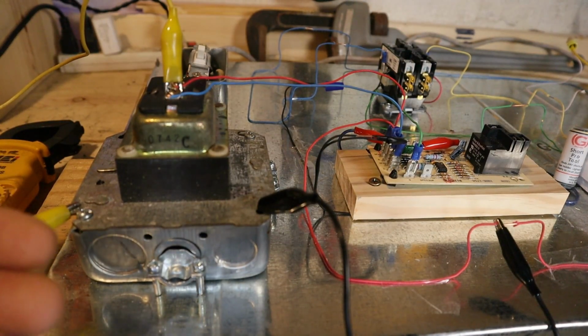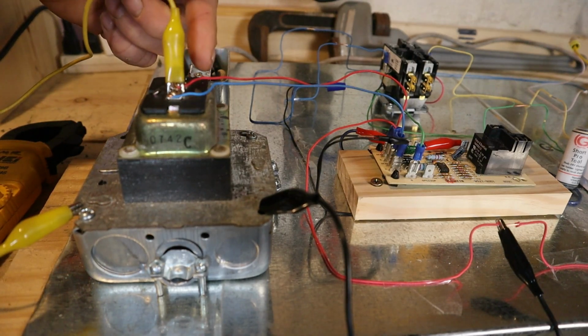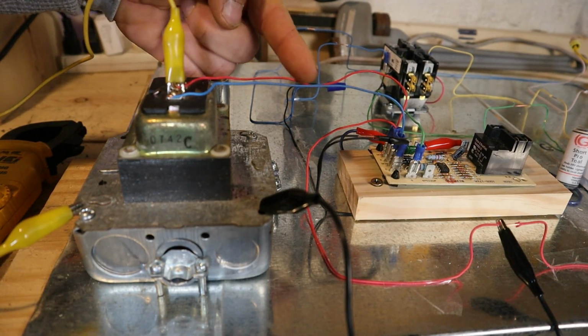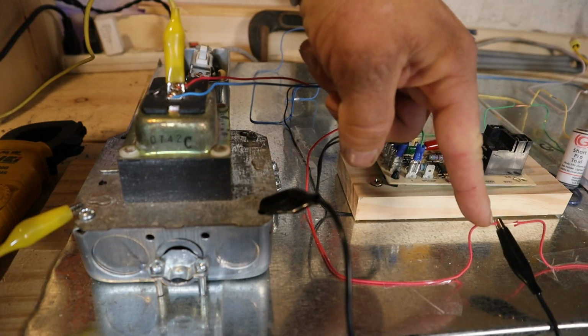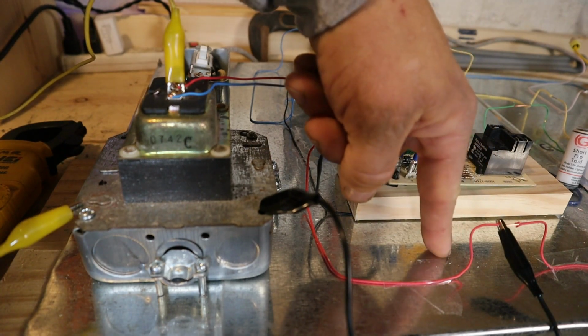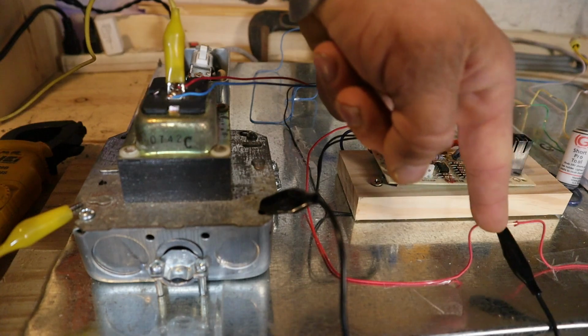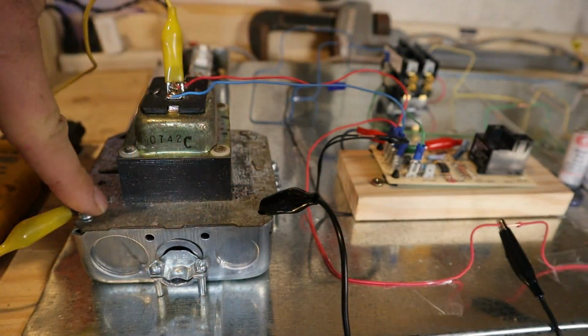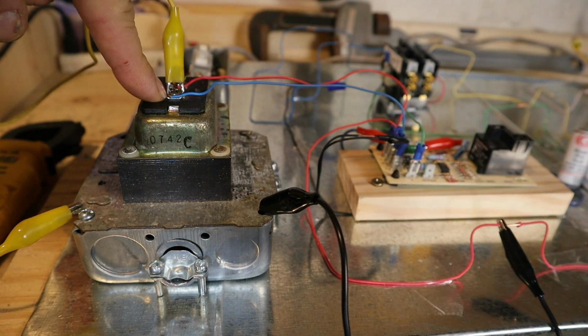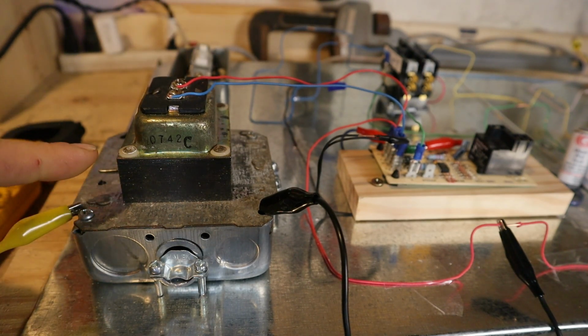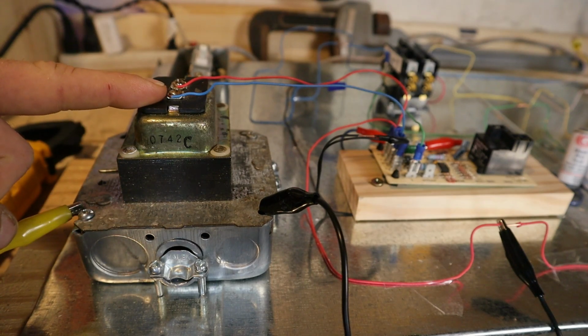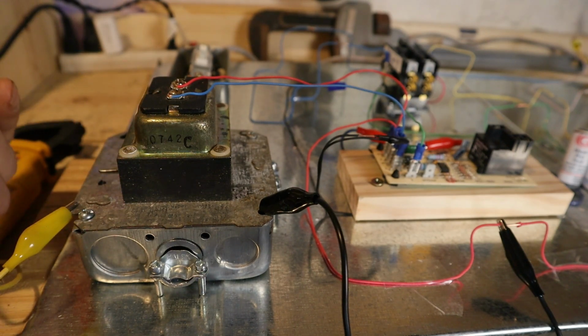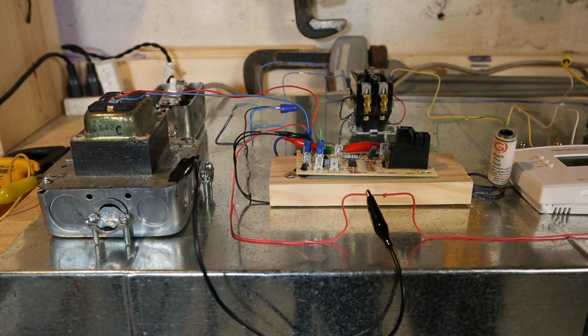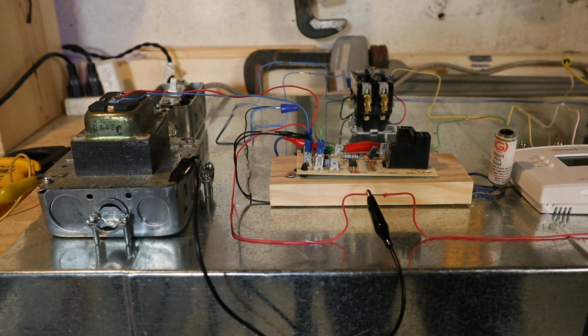Now what all of this essentially means is that we now have a path for 24 volts to leave the load on our transformer and go through the wire. The bare copper on the wire touches metal, which we simulated with our jumper here, and that metal can now connect back to the common, and that's what creates our short circuit. But when we remove that ability for any voltage on the metal to make it to common, we now have a floating circuit that doesn't blow our fuse. Now let me just demonstrate this to you really quickly, and then we'll go into explaining why this is such a great benefit in finding shorts very quickly.